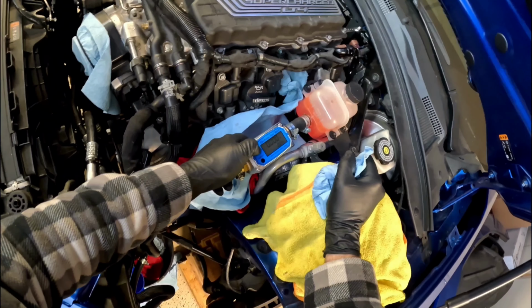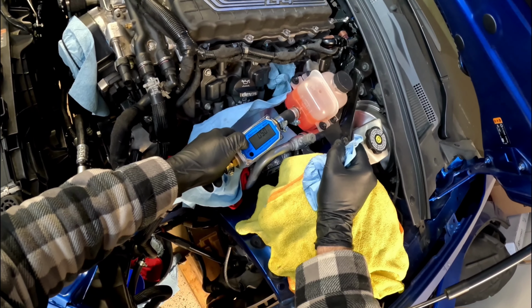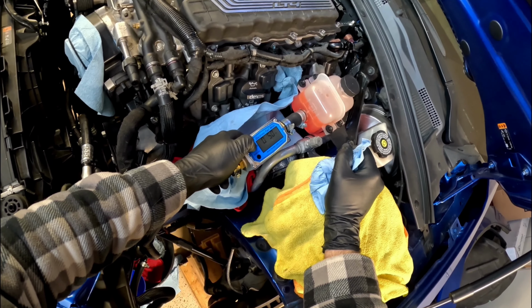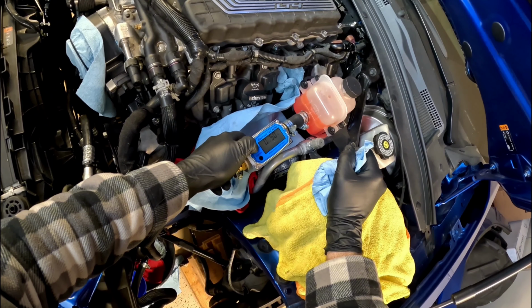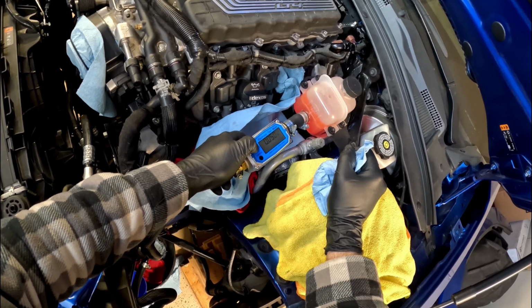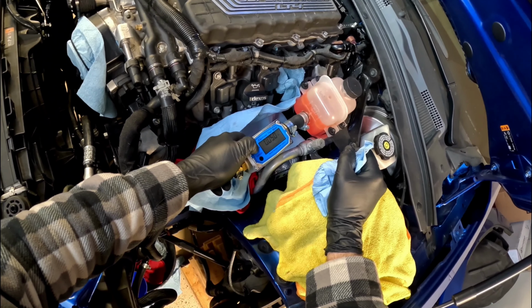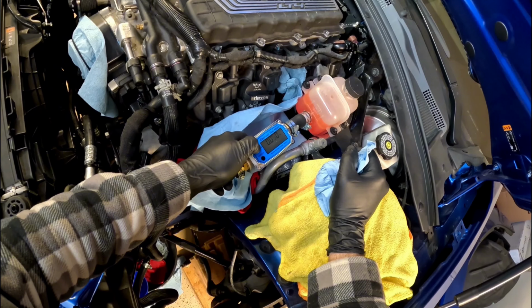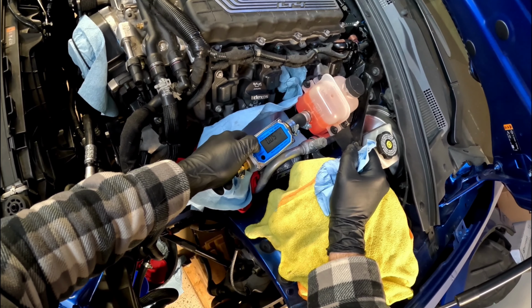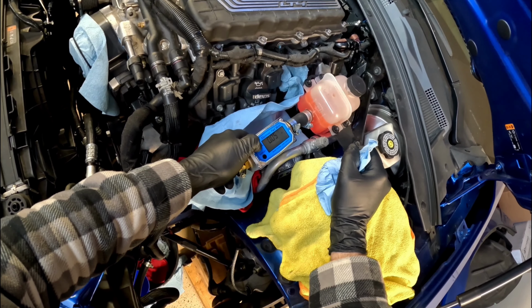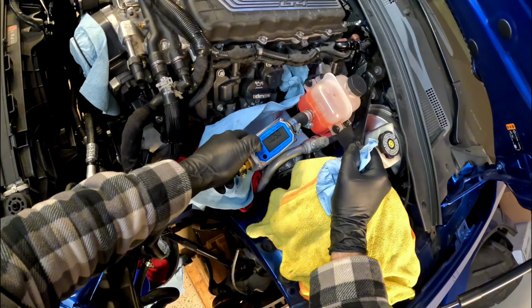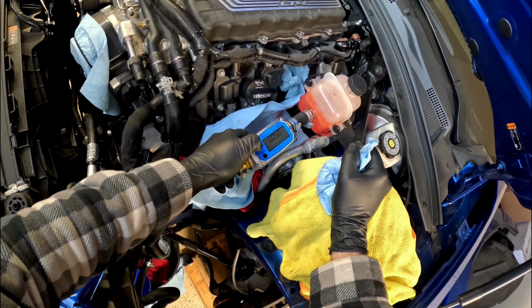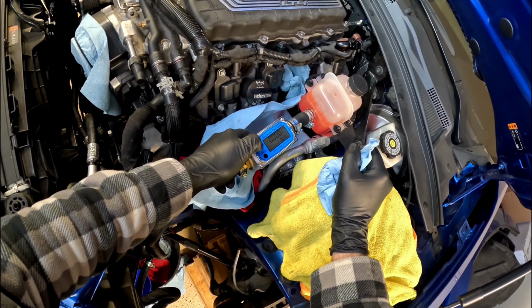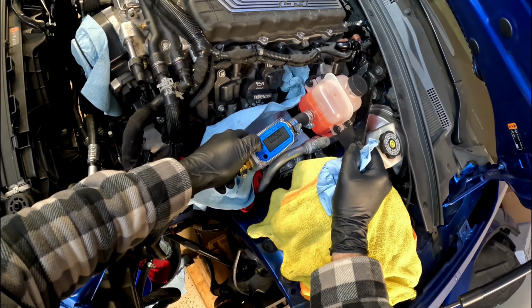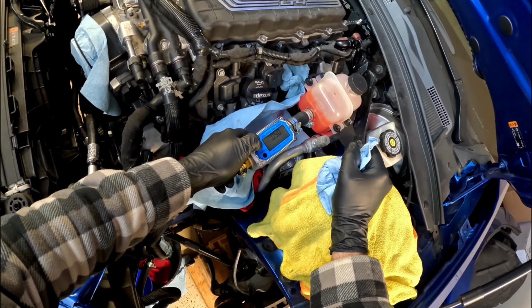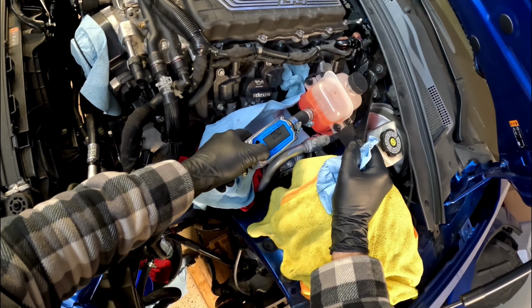Now with this flow meter, if you hold this calibrate button down, a number will come up flashing, and I believe that's the conversion factor. That's telling it how much flow is going through based off of how fast the turbine inside of this flow meter is spinning. Mine came programmed at 0.05. Now talking to my buddy Gabe Griffin, his came calibrated at 1.00. So that tells me that the flow rate I'm showing is actually only 5% of the real flow rate going on.